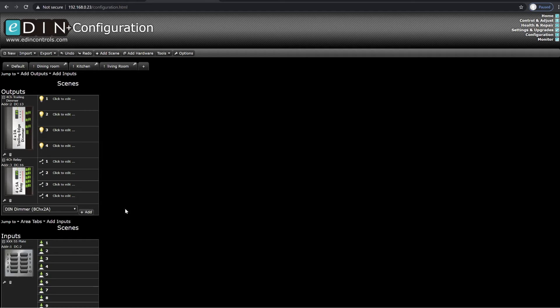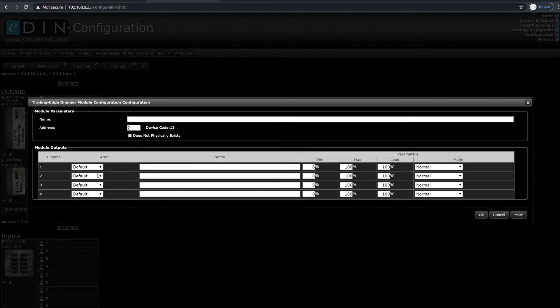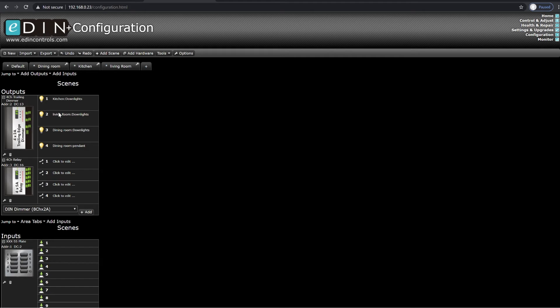This will allow our scene assistant to make some of the basic programming that we require. Starting with the trailing edge module, I hit the spanner option and now I can start putting these four circuits into the areas they belong. In this case, I have a kitchen, a living room on those circuits, and then a dining room on the following ones. Naming is important at this point — the more you can name the circuits, the better off your program will be and easier to read. So I have kitchen downlights, downlights in my living room, and in my dining room I have downlights and one pendant. Then I hit OK and you can see that the naming has changed for each of these circuits and they are ready to go.